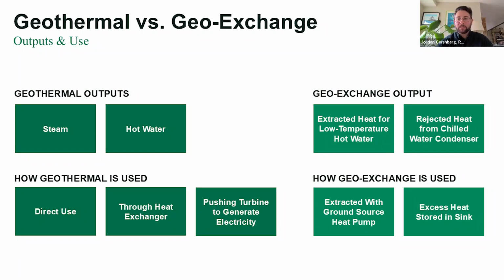Different from that is geo-exchange, and you'll notice the words we use for its output: extracted heat or rejected heat. It's heat we pull out to make low temperature hot water, or heat rejected from a chilled water condenser. Again, it's exchanging heat two ways - heat coming out and heat going back in. It's always used with a ground source heat pump, which becomes much more prevalent in our ongoing conversation, because that heat pump is key to using electric energy to move heat around beneficially. We can also store that excess heat, depending on the balance of heat load the system is connected to.